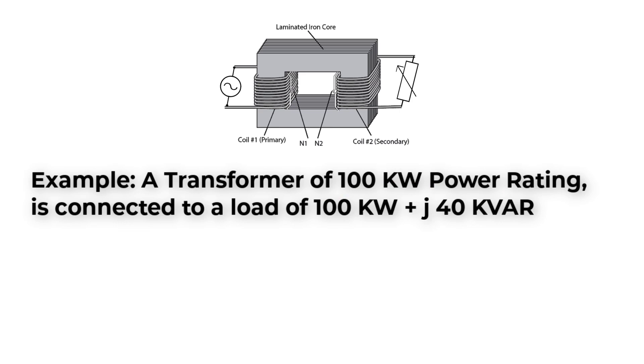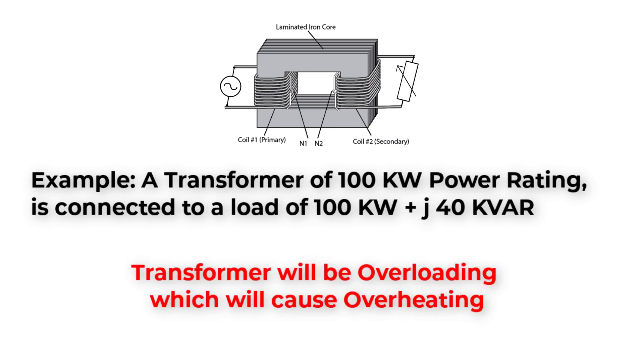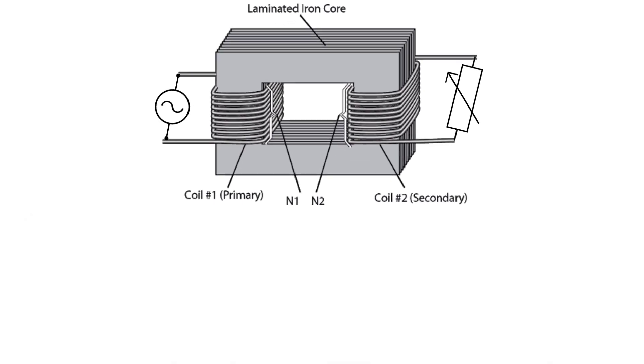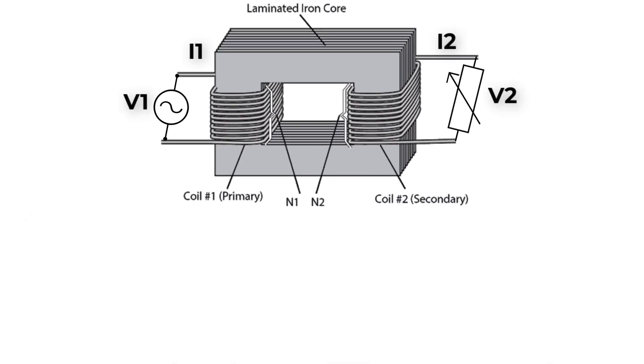according to the 100 kilowatt rating, the transformer is delivering its rated power. It's okay. But actually, we didn't put into our consideration the reactive power, which already exists, and will cause overloading for the transformer.